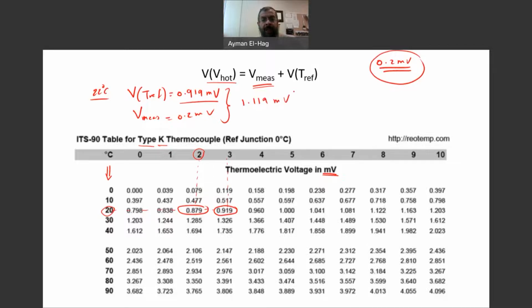That sum is 1.119 millivolt. Now we want to find the temperature corresponding to this voltage. Looking at the table, 1.119 falls between two values, corresponding to a temperature between 27 and 28 degrees. We can use linear interpolation to find the exact temperature, so it will be 27 point something.